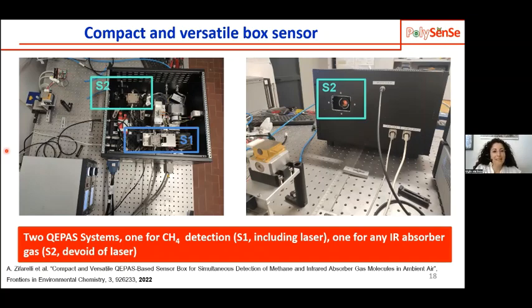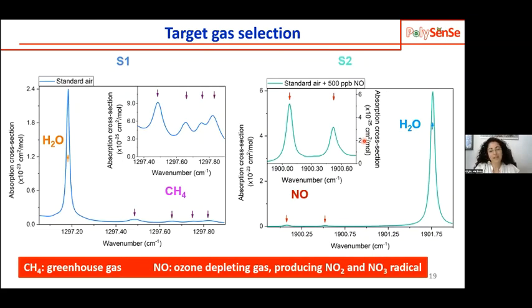This configuration makes the sensor extremely versatile, because depending on the application, depending on which gas molecule we need to detect together with methane, we just select the proper laser source, we collimate it on the focusing lens, and we perform our measurement. So this box can be used to detect methane and any gas which has absorption features within the infrared spectral range. We demonstrated the operation of this box for environmental monitoring purposes. We detected methane together with nitric oxide, which is an ozone depleting gas. With both sensors, we were also able to detect water.